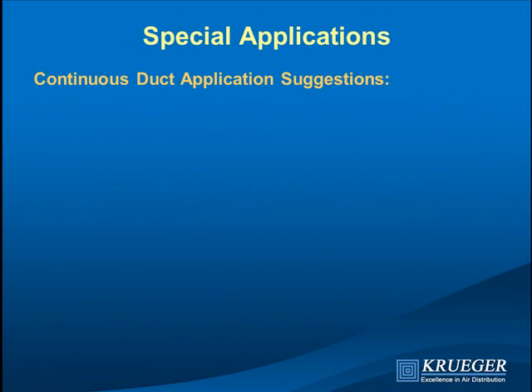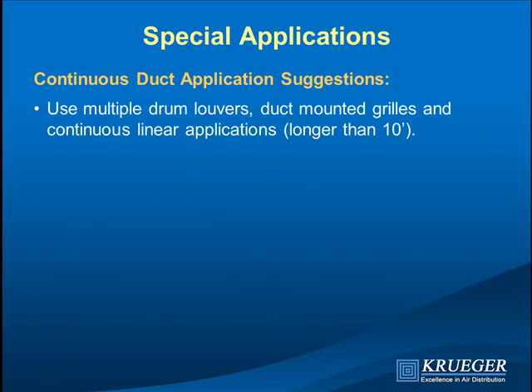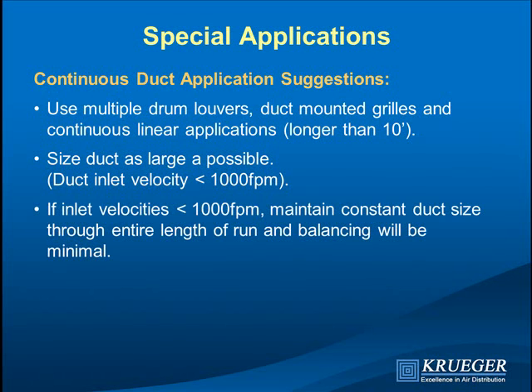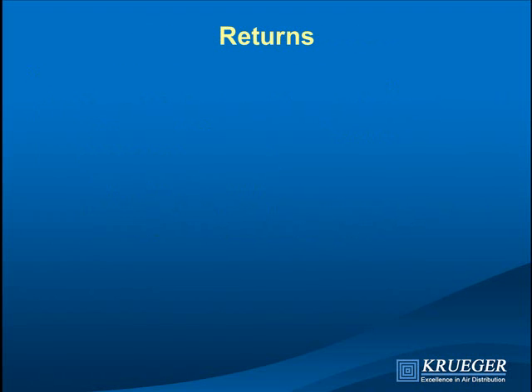A special application is a continuous duct with multiple grills — duct-mounted grills, grills on boots, or drum louvers. Balancing them can be tricky; at high velocity, the first diffuser can actually draw air into the duct instead of blowing out. Use multiple drum louvers if the run exceeds 10 feet. Size the duct so inlet velocity is no more than 1,200 feet per minute — 1,000 would be better — and keep the duct that size all the way along without stepping it down. Static regain then provides constant static pressure down the duct, making the diffusers self-balancing.